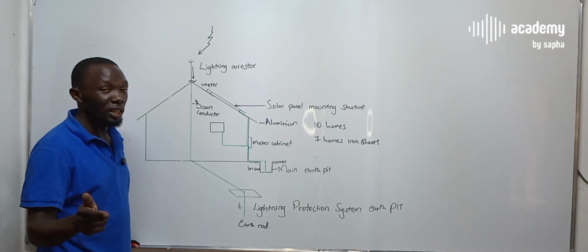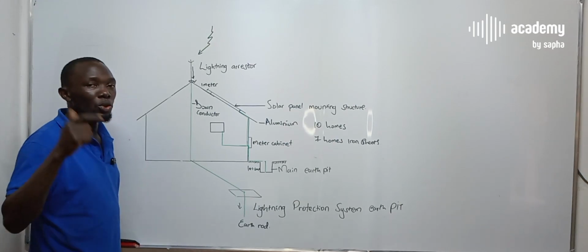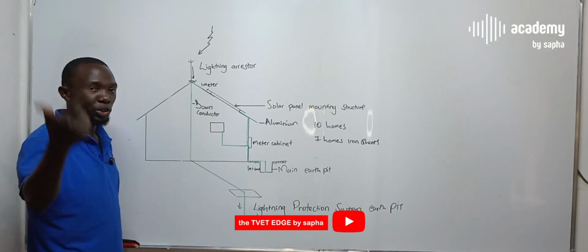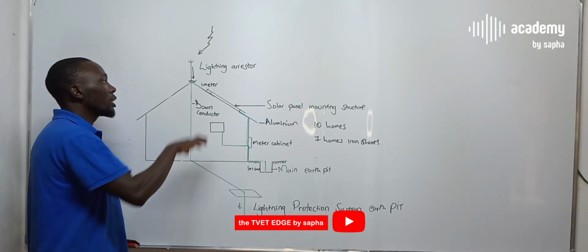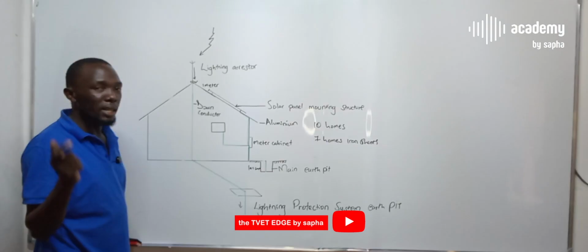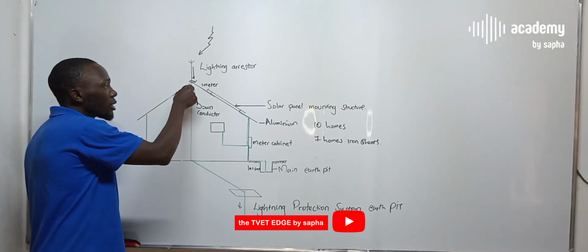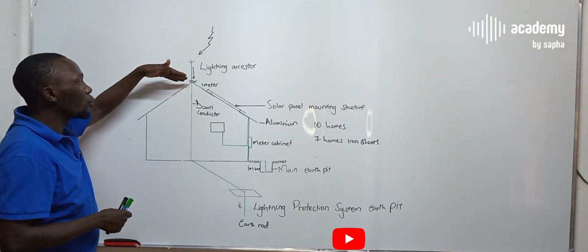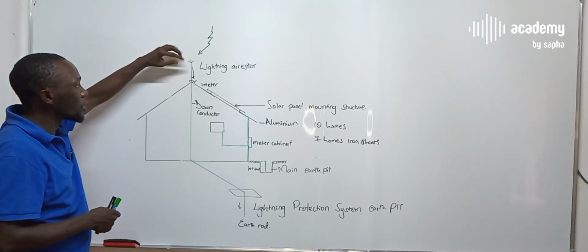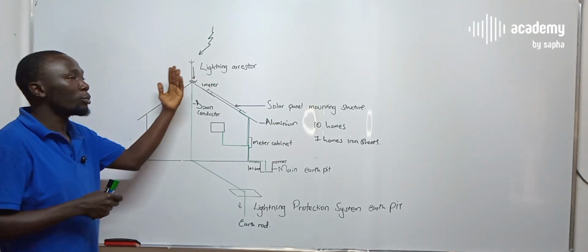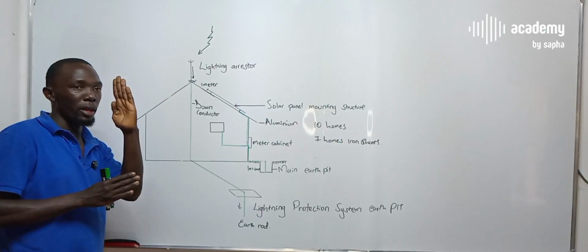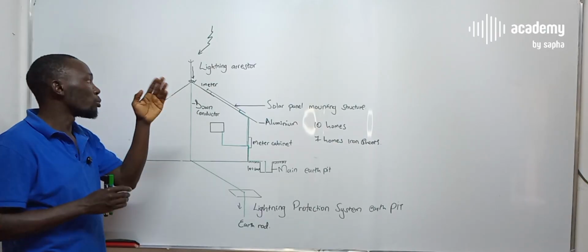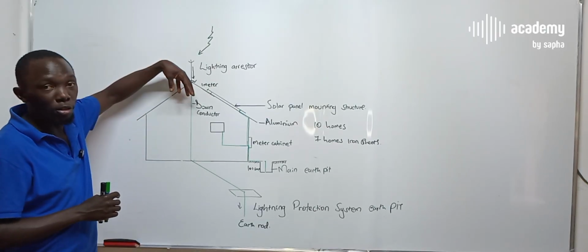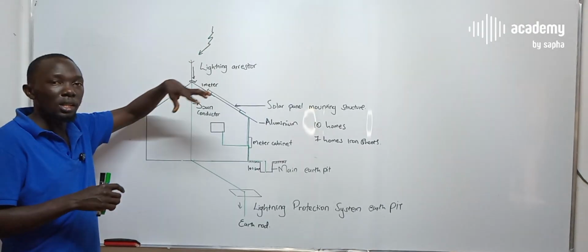For small roof structures, you need a cable with high voltage insulation to ensure that in case a strike happens, that cable - because a section of it will lie over the roof, since the arrestor in most cases is not at the edge of the roof, it could be at the center when viewed from above.